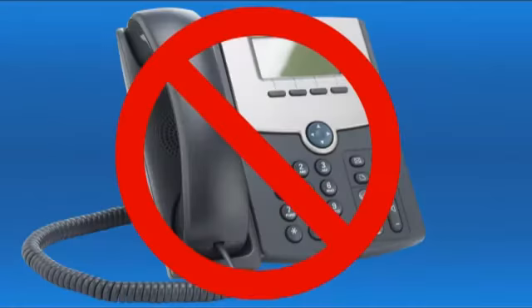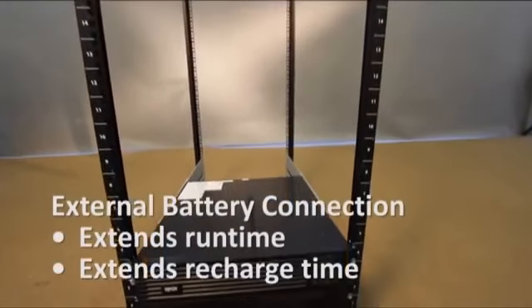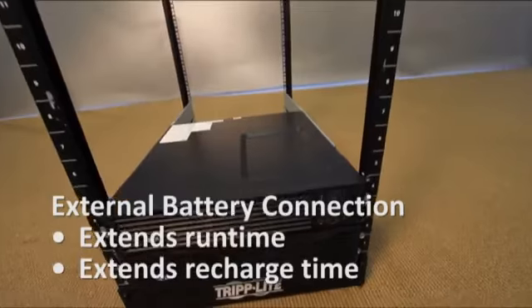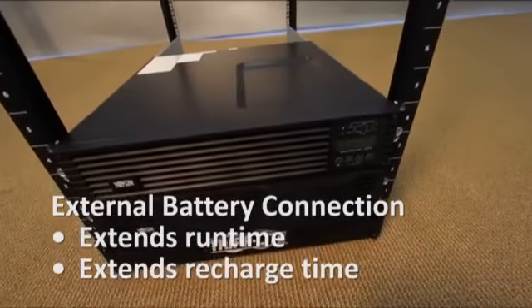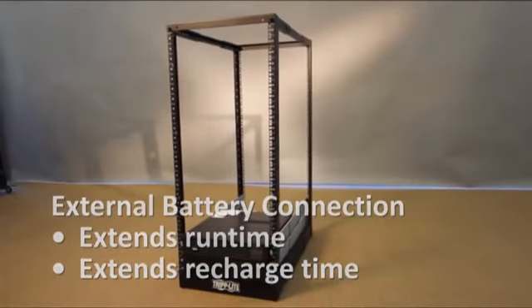The EPO port is not a phone line surge suppressor. Do not connect a phone line to this port. All models accept additional external batteries to extend the runtime of the UPS systems. Note that adding external batteries will naturally increase recharge time as well.